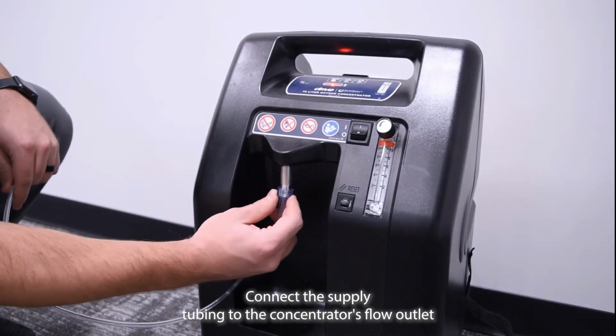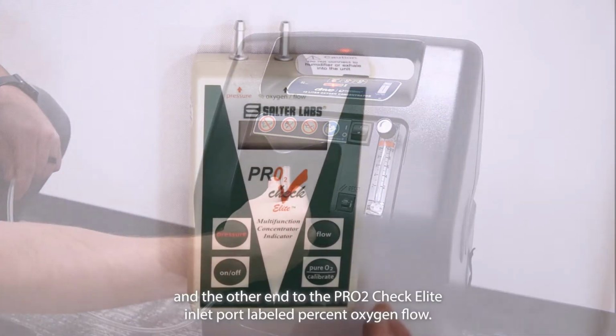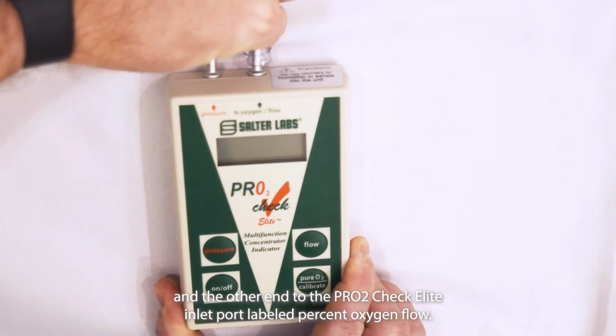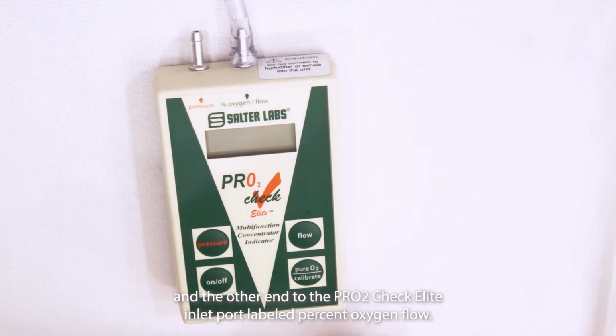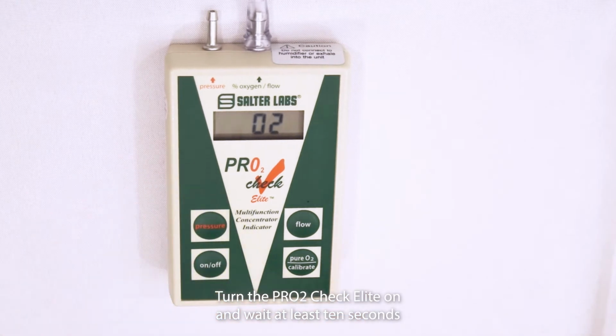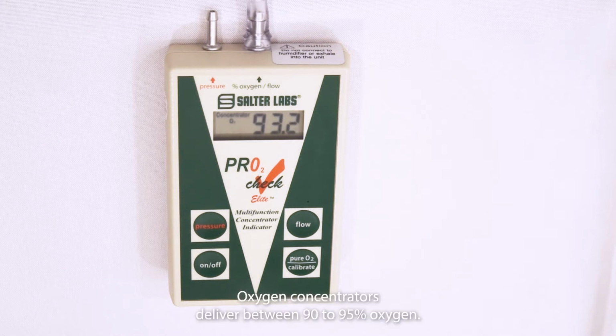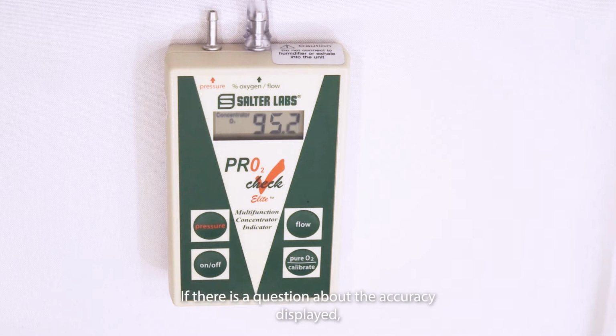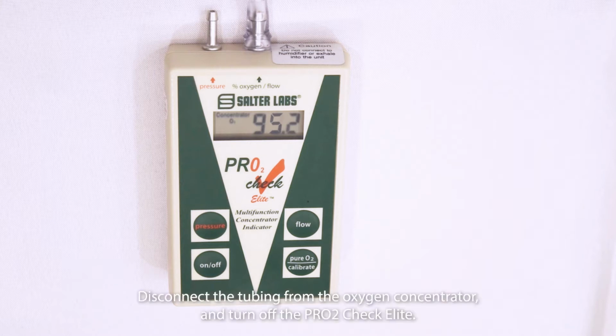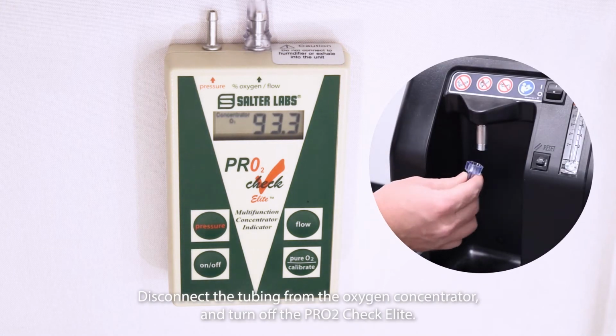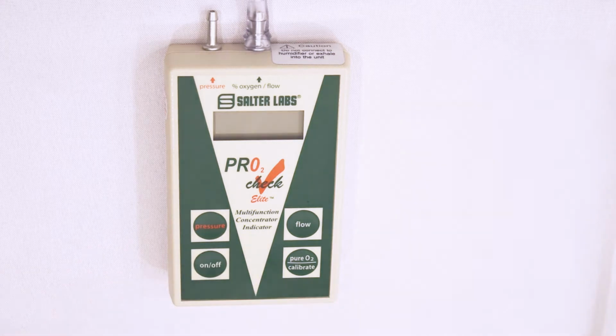Connect the supply tubing to the concentrator's flow outlet and the other end to the PRO2 Check Elite inlet port labeled % oxygen flow. Turn the PRO2 Check Elite on and wait at least 10 seconds for the oxygen percentage reading to stabilize. Oxygen concentrators deliver between 90 to 95% oxygen. If there is a question about the accuracy displayed, do a quick one-step calibration procedure and repeat the reading. Disconnect the tubing from the oxygen concentrator and turn off the PRO2 Check Elite.